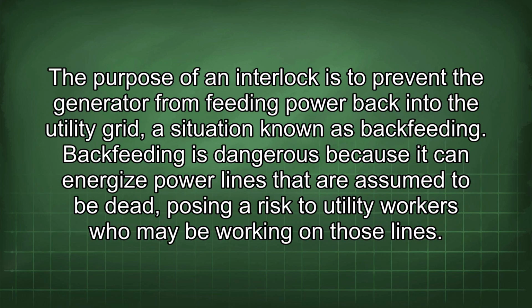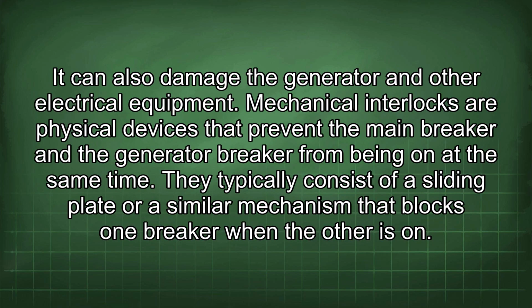The purpose of an interlock is to prevent the generator from feeding power back into the utility grid, a situation known as backfeeding. Backfeeding is dangerous because it can energize power lines that are assumed to be dead, posing a risk to utility workers who may be working on those lines. It can also damage the generator and other electrical equipment. Mechanical interlocks are physical devices that prevent the main breaker and the generator breaker from being on at the same time. They typically consist of a sliding plate or a similar mechanism that blocks one breaker when the other is on.